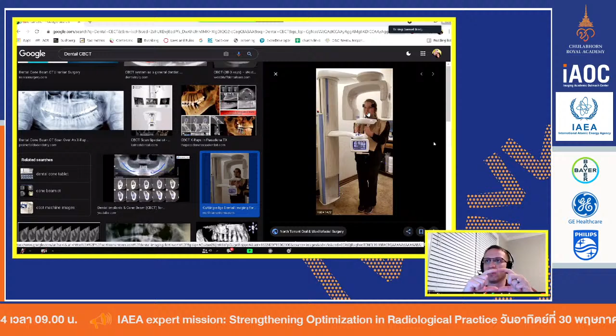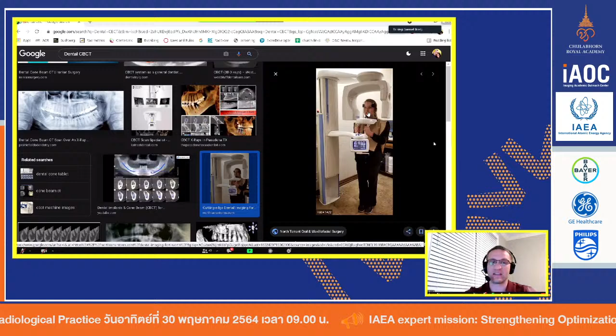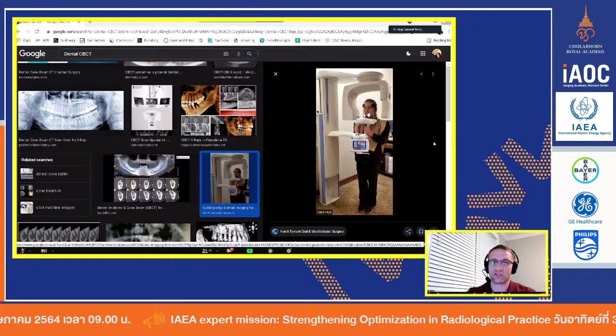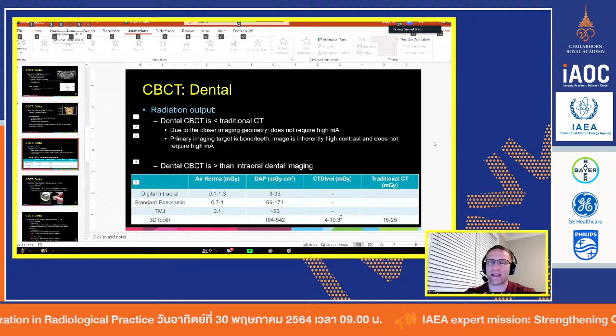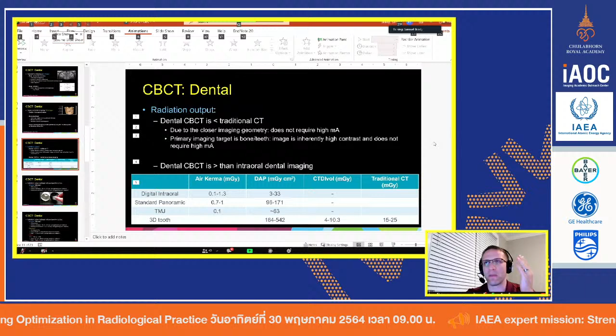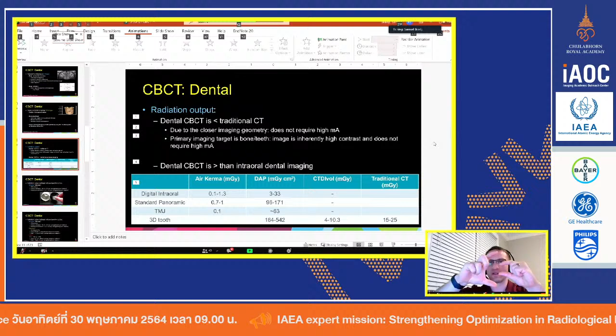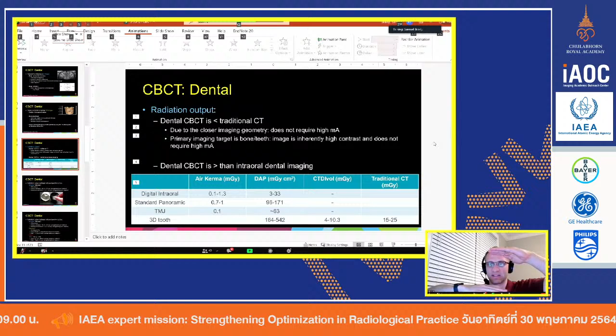Then you'll know if your 10 centimeter ion chamber will cover that, or if the field of view is larger, because maybe your system is larger. If that's the case, there's nothing else you can do. You still use the chamber and still make the calculation, but you have to know that these two numbers will not be as accurate to compare. A traditional CT scanner, when we calculate CTDI for a maxillofacial or more coned-in protocol, will have maybe 4 or 8 centimeter fields of view, which are always going to be smaller than the 10 centimeter chamber, unless you're using one of the newer systems with 160 slices, or 16 centimeters.